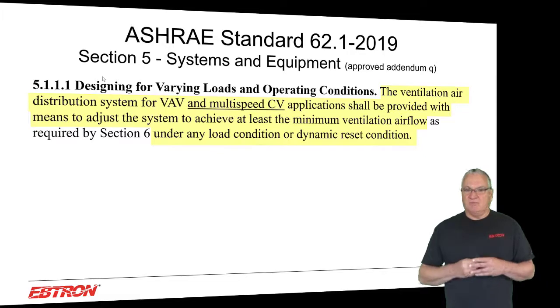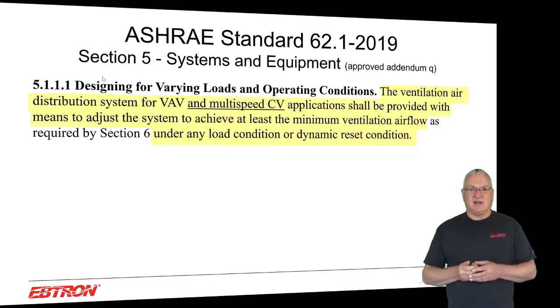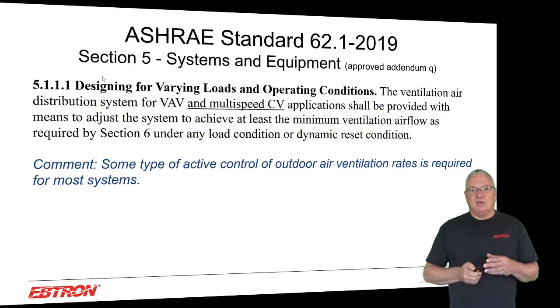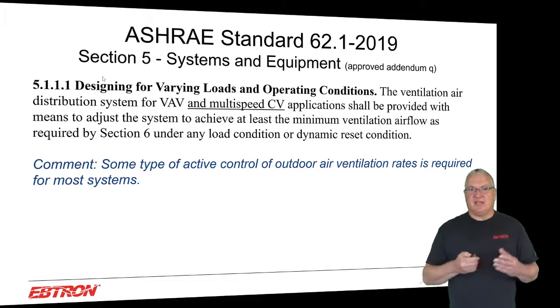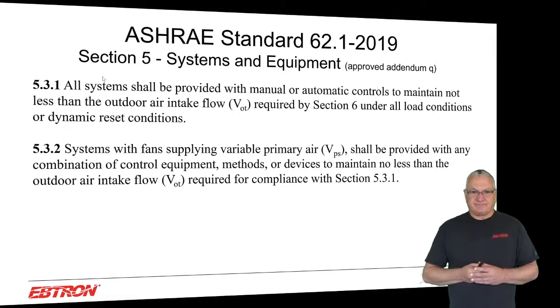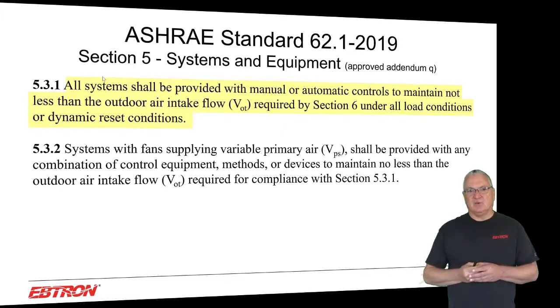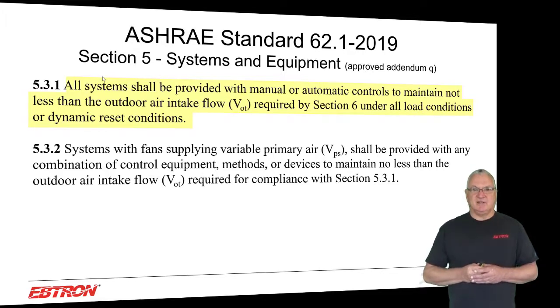Multi-speed constant volume systems are now the norm, whether they be constant volume air handlers, multi-speed fan coils, or whatever it is. So you have to do some type of active control of outdoor air ventilation rates on most of these systems — you just can't set it and forget it. All systems shall be provided with manual or automatic controls to maintain not less than the outdoor air intake flow required by section 6 under all load conditions or dynamic reset conditions — so on VAV as load varies, and on DCV systems as dynamic reset conditions vary.